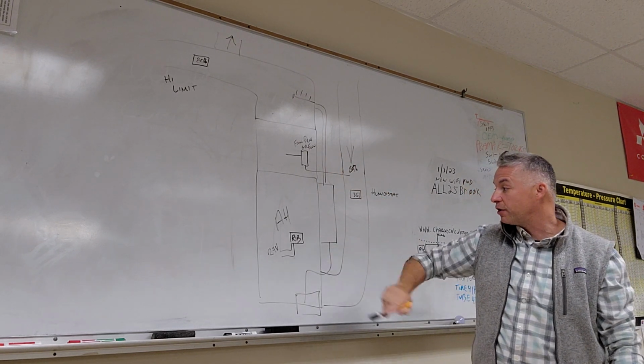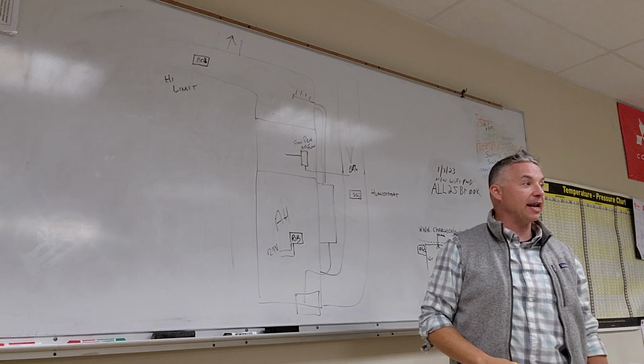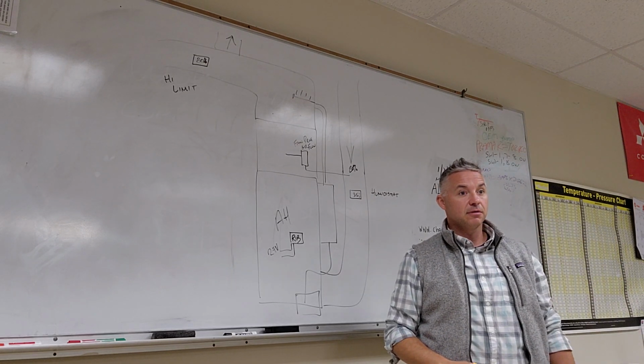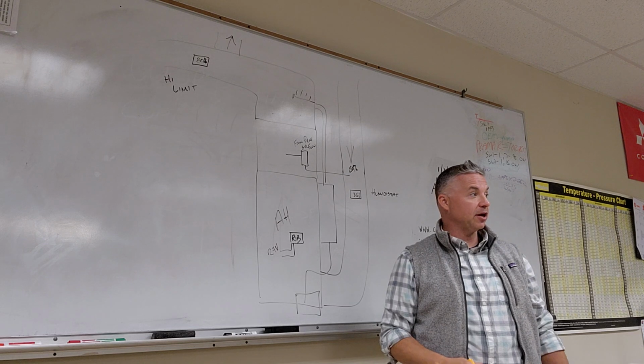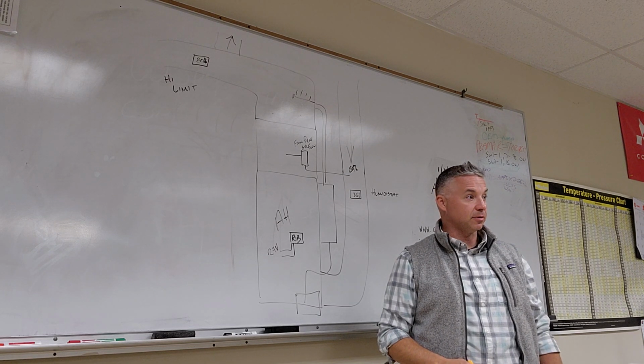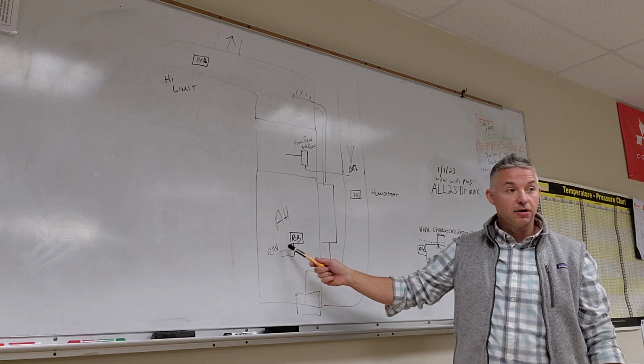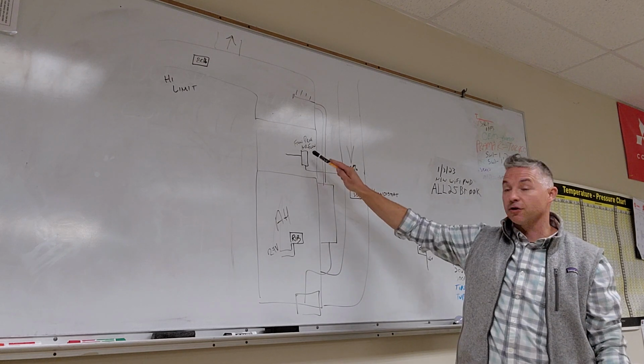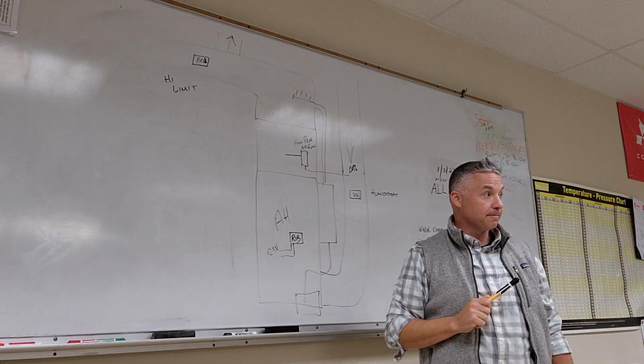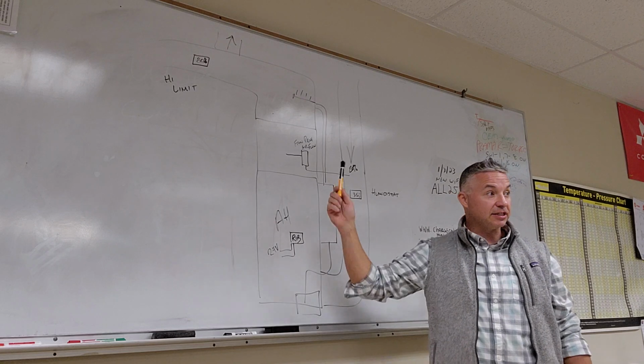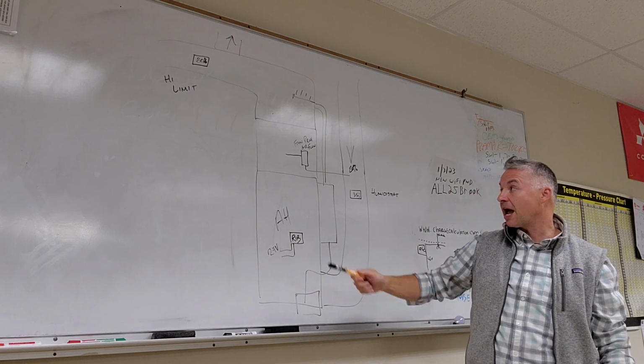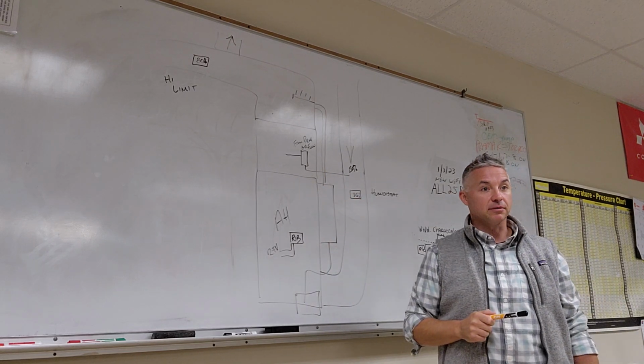Is it possible to have 24 volts going to the fan and no airflow? Yeah, your blower motor's no good. Bingo, right? It's possible to create a 24 volt call, which is why the airflow switch is still necessary. Not only do you want to turn the fan on, but you want to prove that it came on.